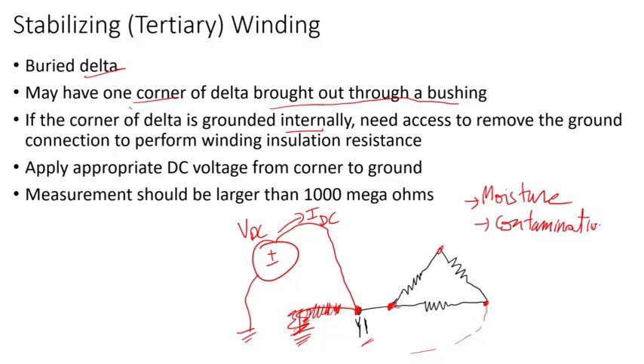You're testing for moisture and contamination - the health of the insulation. Theoretically the insulation is supposed to be perfect, but that's not the case. Things can happen when you ship the transformer from the factory to the destination substation, or move it from storage to the substation. Things will happen and cause somehow an unintentional ground.